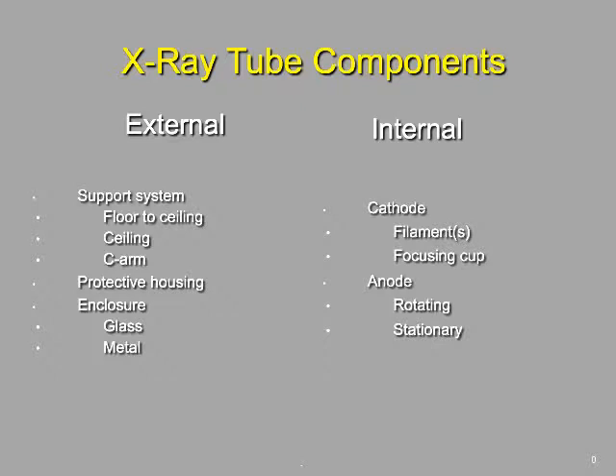Around the x-ray tube there's going to be some kind of support system — either a floor-type, ceiling-type, or a C-arm mobile support system. In addition, it will have protective housing around it. That protective housing serves two purposes: to protect the tube itself, and to protect us from x-rays. It is generally made out of lead, which is the main reason these tubes are so heavy.